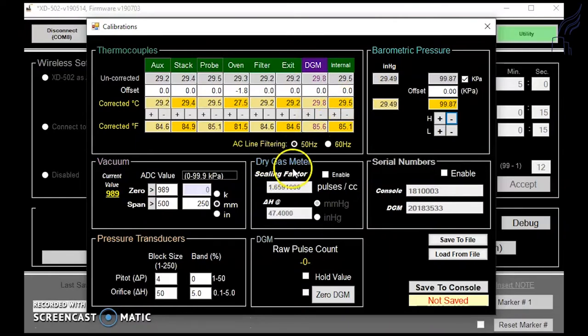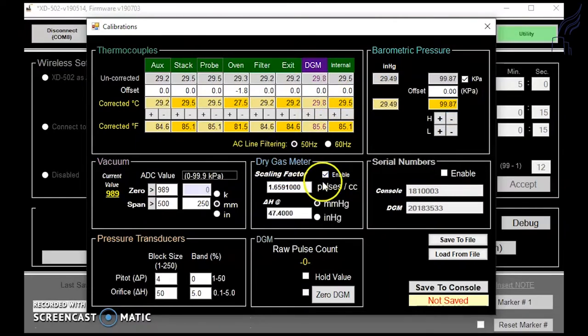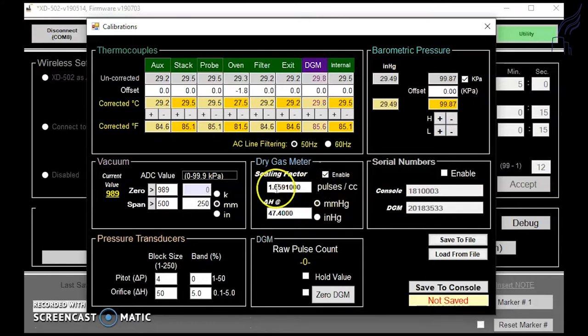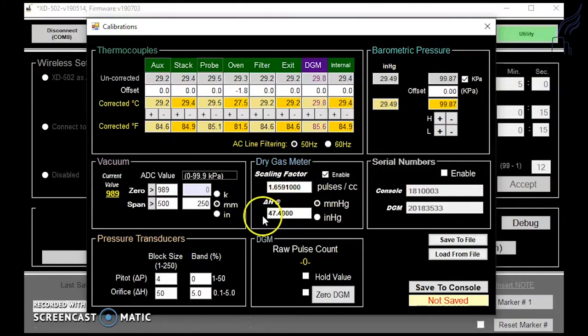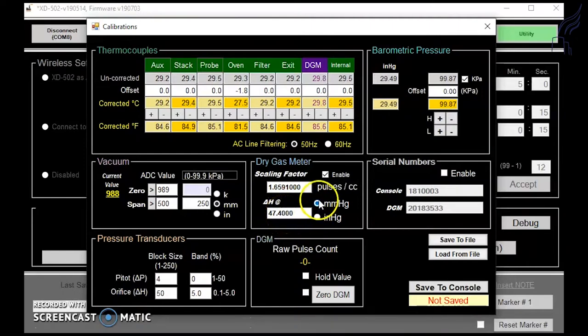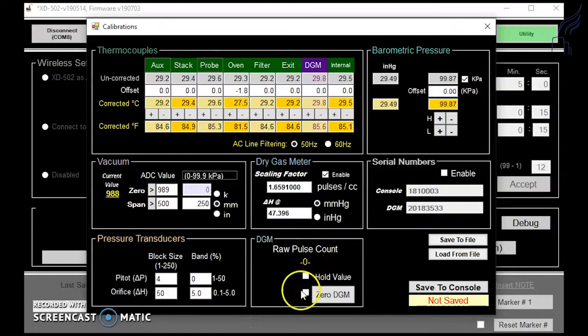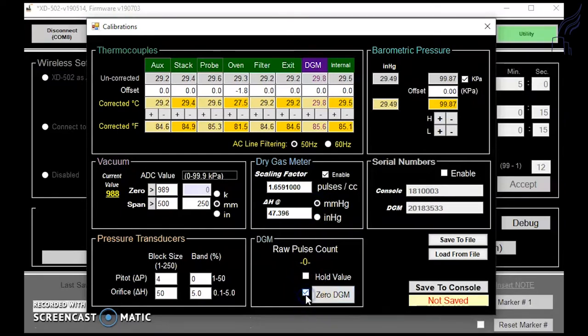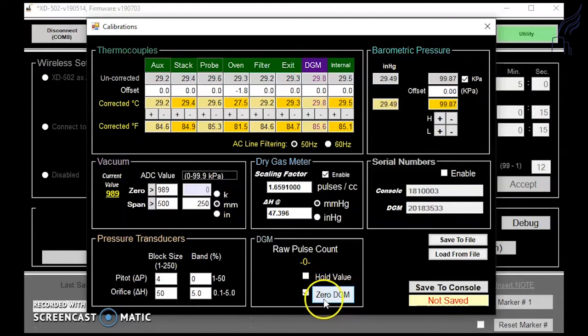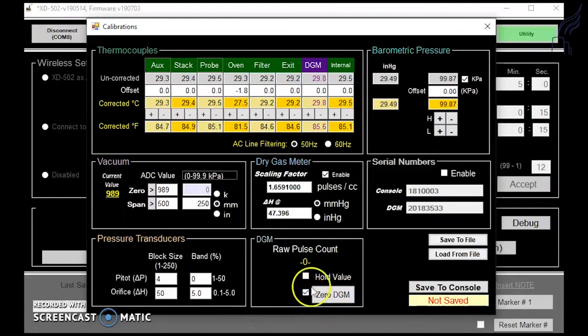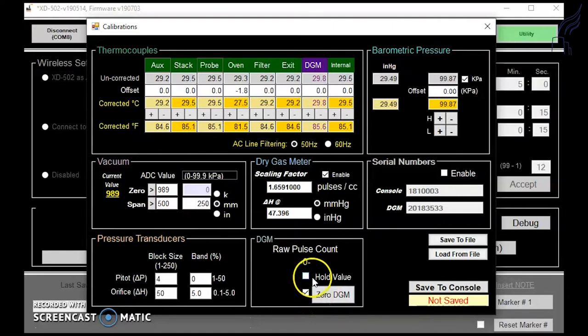For the dry gas meter, when you click enable here, you can insert your correct scaling factor and delta H sub at into the boxes here. You can also change the units if you need to. You can zero your dry gas meter by clicking the box here and then clicking on the zero DGM tab if you need to or click in the box here if you need to hold a value for the dry gas meter.